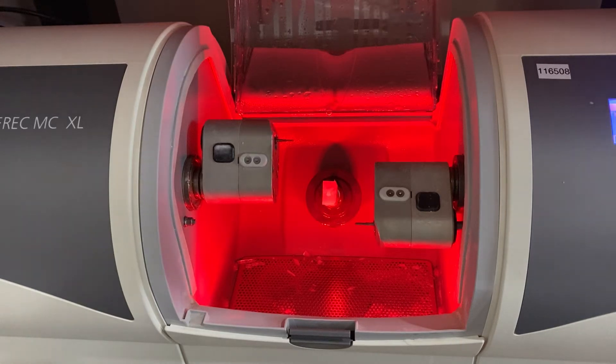Okay team, today we are going to replace a burr on the CEREC. We got an error message that lights up red. Today's message says the instrument cylinder pointed burr 12s is defective, please replace it and press start to continue.